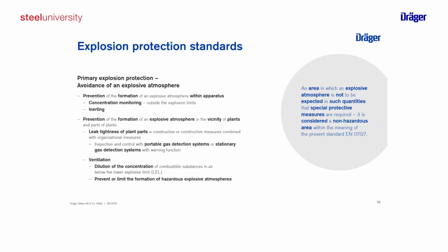So if we have a cylinder filled with hydrogen, for example, and the quantity in the cylinder is as much, and if this were leaking in a closed room, then we need to consider: is the quantity of explosive atmosphere so high that, in case of an explosion, there would be damage to persons or to the building? Then we are at a level which is dangerous. But if this were stored outside and released and diluted by fresh air, then there is not the risk that we have high quantities.